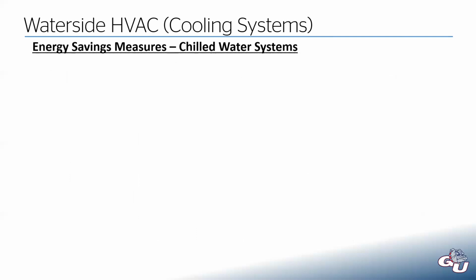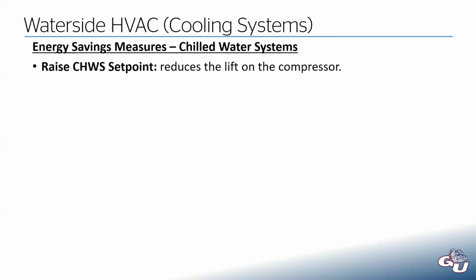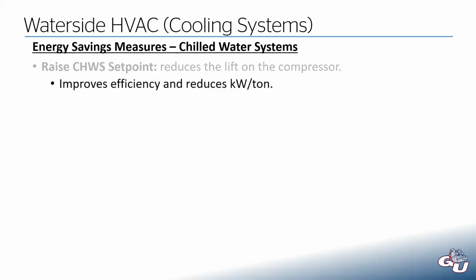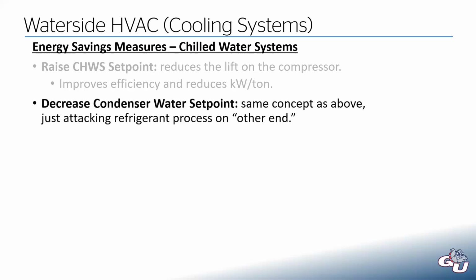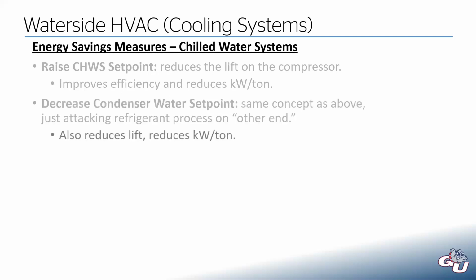And last slide for you, then I can let you go. You could try and raise the chilled water supply set point. As we just discussed, that'll reduce the lift on the compressor, give you better efficiency by reducing the kW per ton. You can try to decrease your condenser water set point, same idea. Also going to reduce lift.